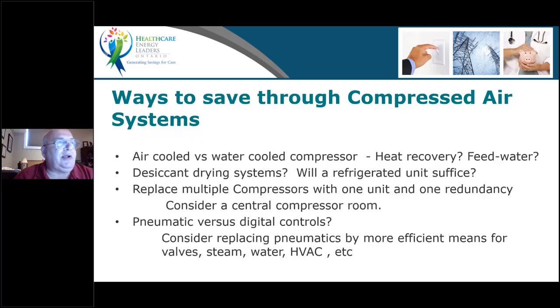So we look at other ways when it comes to compressed air systems. Do we consider air-cooled compressors versus water-cooled? Can we look at heat recovery? Can we use some of that water-cooled on a compressor for feed water to a boiler? Drying systems, what is the minimum requirement of the compressed air dew point? Do we need a desiccant dryer? Do we need a refrigerant dryer? Are we looking for oil-free, general purpose air? There are so many questions to ask when it comes to drying systems, and yet they all affect how the compressors work and the air quality that goes to these controls.